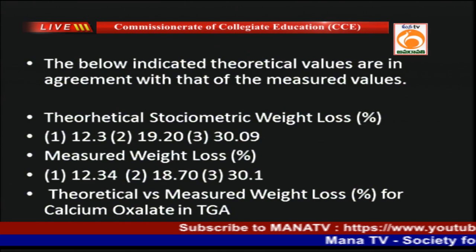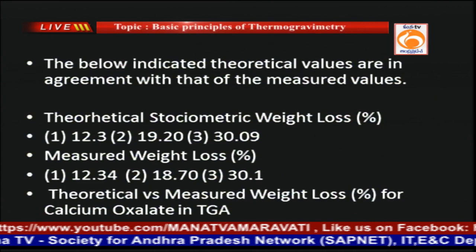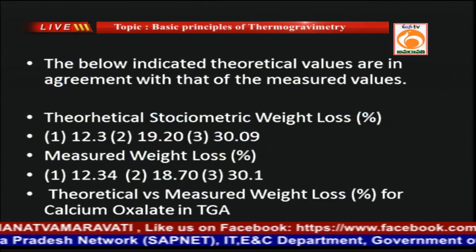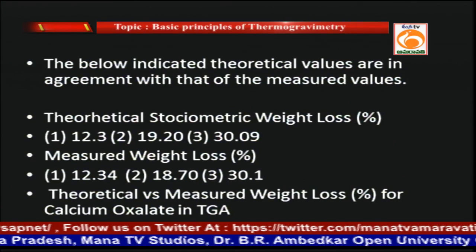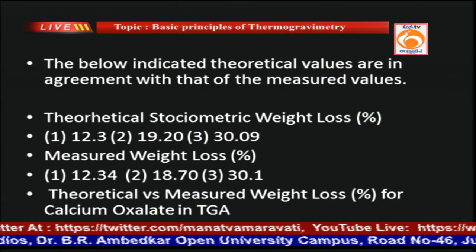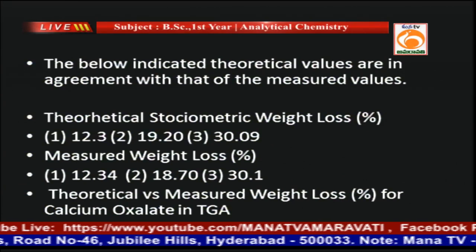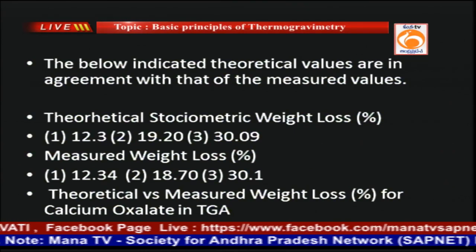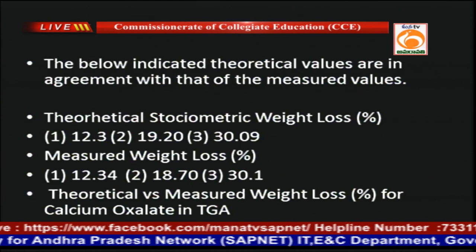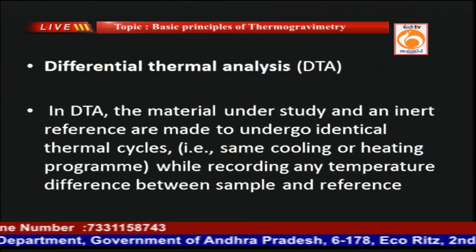as a calibration standard for both the techniques. First, you compare theoretical stoichiometry, which indicates 12.3 percent loss, for example, water molecules. Second, the measured weight loss in your practical is 12.34. Likewise, if you compare, the difference between theory and practical remains so close that we can take it for granted that the particular equipment is working in proper condition. So remember, my dear students, the calcium oxalate compound will be studied to know the efficacy or accuracy of the equipment.